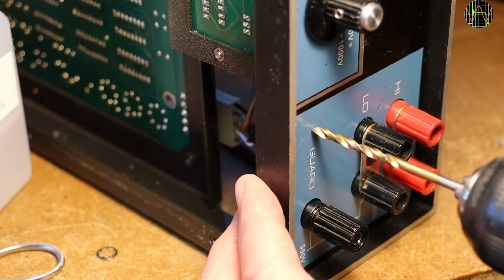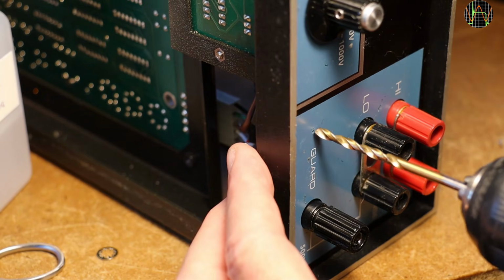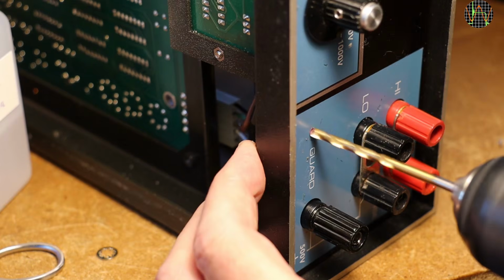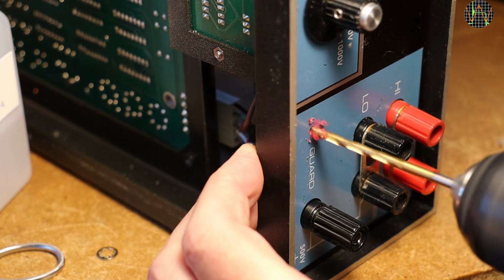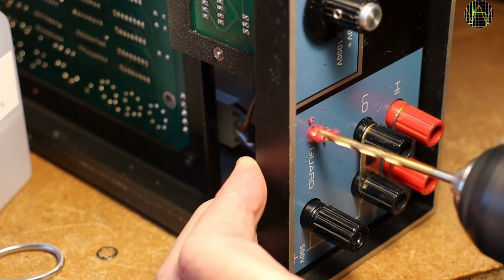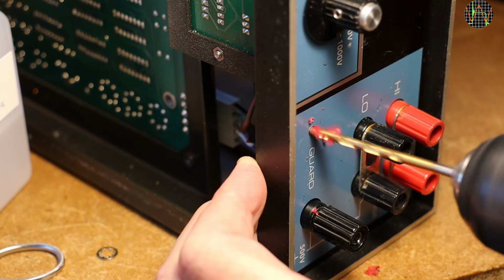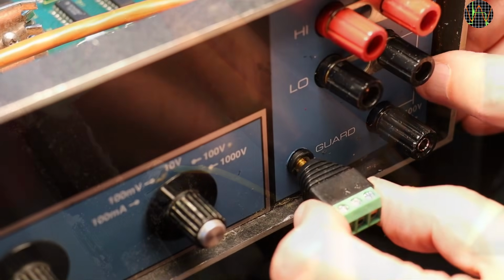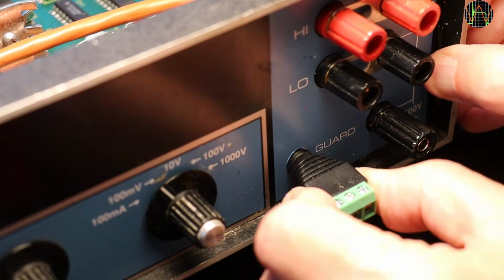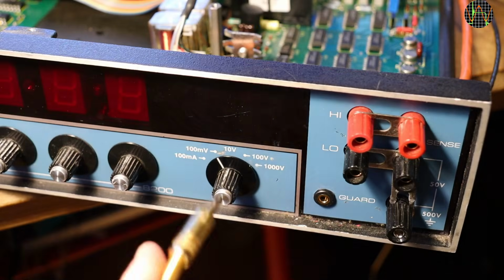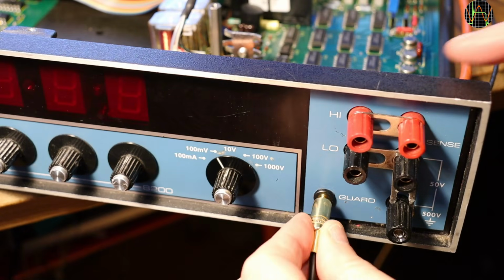I mentioned already that the millivolt output is only on the rear, which is rather inconvenient if the unit is in a stack of other devices. I decided to add a millivolt output on the front, for which I'm drilling a hole here. It's for a 3.5mm stereo jack, allowing for guard, low and high. I can either use an adapter like this or a shielded cable with banana plugs on the end.